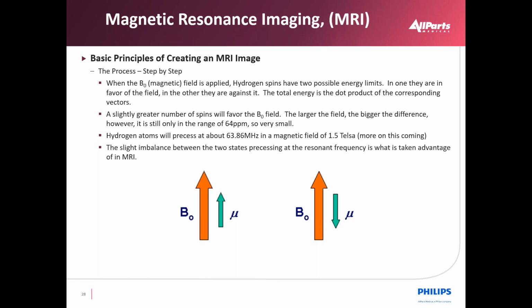This is why copper is used to shield MRI rooms. It keeps extraneous signals out so that the equipment will mainly focus on the MRI signal. The slight imbalance between these two states is what is used in MRI imaging. Hydrogen atoms will precess at a specific frequency, the system resonant frequency, which is approximately 63.86 megahertz in a 1.5 T magnet.